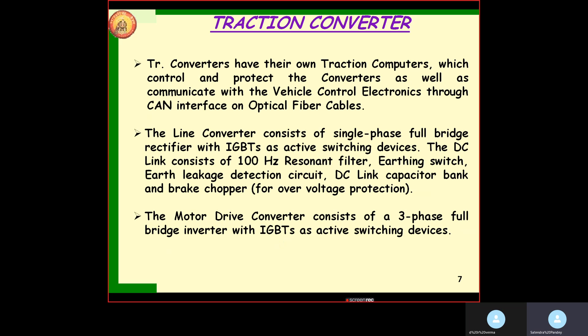Traction converters have their own traction computers which control and protect the converter, and also communicate with SV1 — the vehicle control electronics — through the CAN interface and optical fiber cable. The line converter is a single-phase full-bridge rectifier, IGBT-based. The DC link is a 100 Hz resonant filter which includes the earthing switch, earth leakage circuit, DC link capacitor bank, and brake chopper. The motor drive converter is a three-phase full-bridge inverter, IGBT-based switching device.